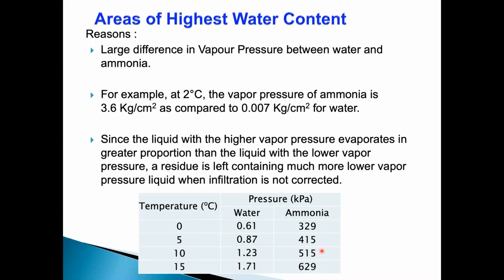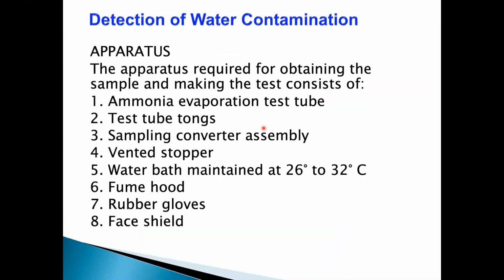So when water comes into the evaporator side, even though at a suction pressure of, say, 3.6 kg at 2 degrees the ammonia will evaporate, the water will continuously remain in the system, and that water starts accumulating.